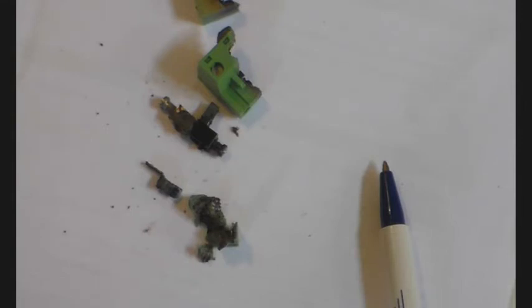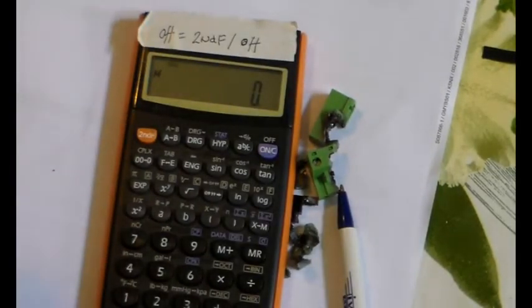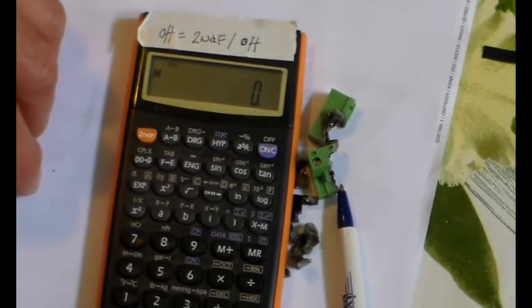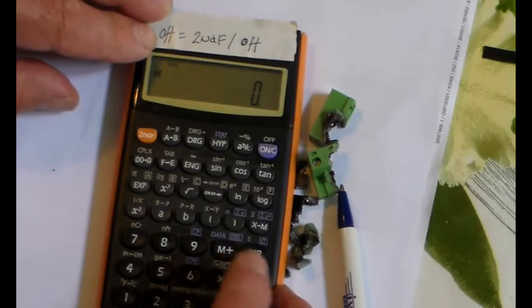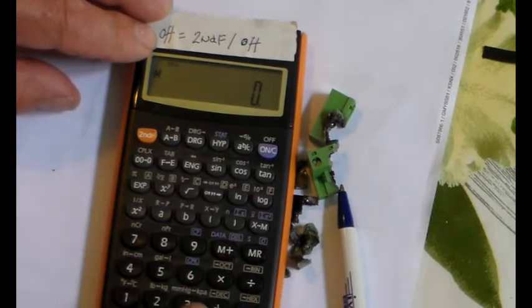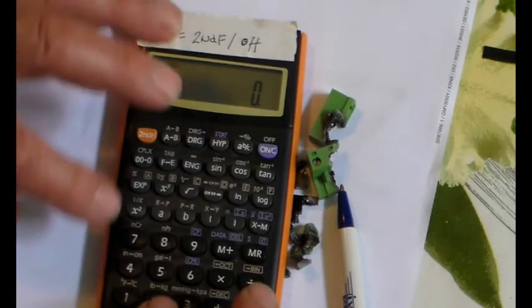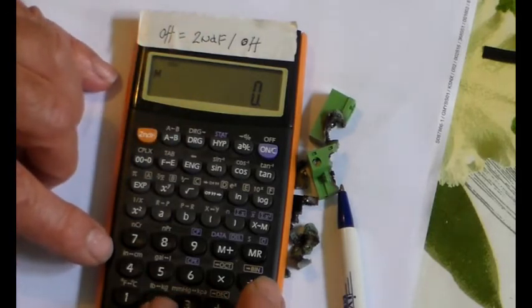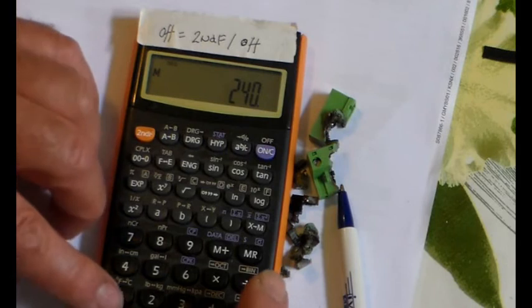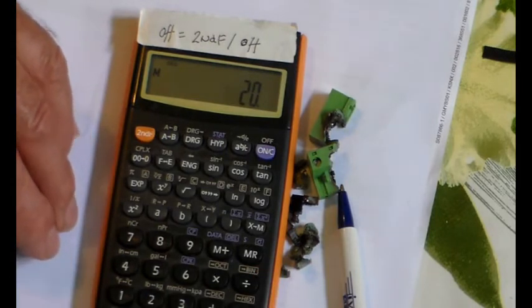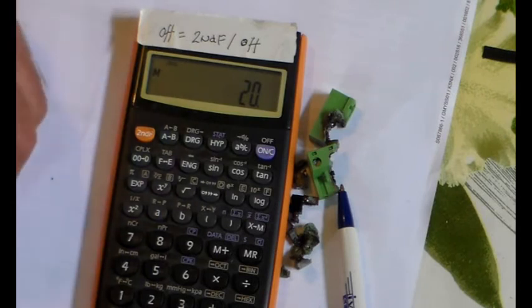I think the math goes like this: 3 kilowatt, there's 4 amps to the kilowatt at 240 volts, so that's theoretically 12 amps. So we got 240 divided by 12 equals 20 ohms, 19 ohms, 20 ohms, that sort of thing.